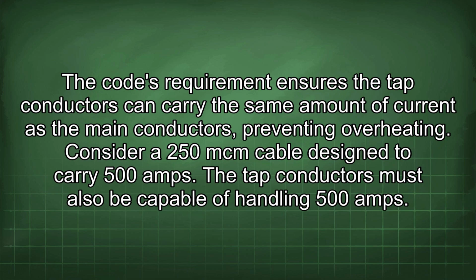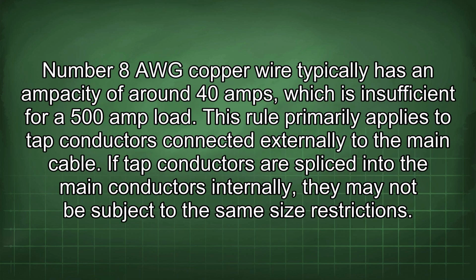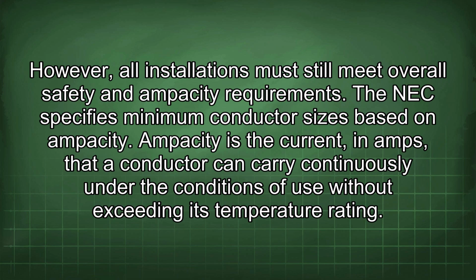Consider a 250 MCM cable designed to carry 500 amps. The tap conductors must also be capable of handling 500 amps. Number 8 AWG copper wire typically has an ampacity of around 40 amps, which is insufficient for a 500 amp load. This rule primarily applies to tap conductors connected externally to the main cable. If tap conductors are spliced into the main conductors internally, they may not be subject to the same size restrictions. However, all installations must still meet overall safety and ampacity requirements.